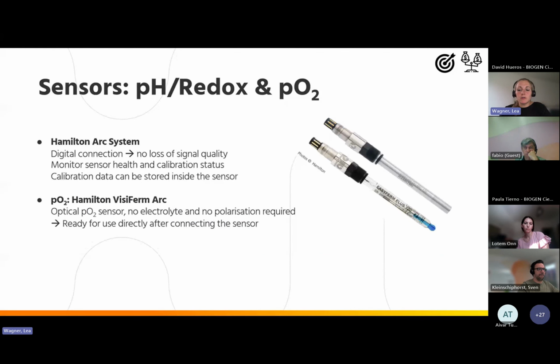Then, as a standard, there's always a pH or redox and a pO2 sensor in the Minifors 2. This is standard. The customer can just choose between Hamilton and Mettler, or a mixture of both. The Hamilton ARC system in general has a digital connection, which has the advantage that there's no loss of signal quality. The sensor health can be monitored, and the calibration status, and the calibration data can also be stored inside the sensor. So before the customer starts the process, the customer can see if the sensor still has good quality or very low quality, and then has the chance to exchange the sensor before it breaks, maybe during the bioprocess.